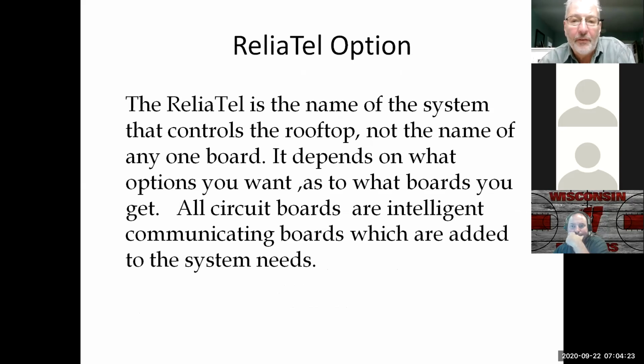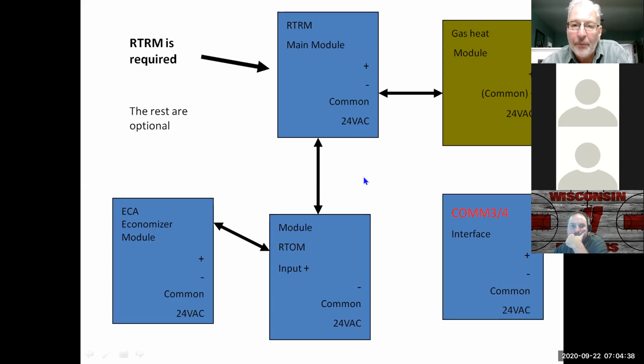All right, Reliatel is the name of the system that we're currently using on the rooftop. What it does is you can add or take out boards and configure the unit to do different things. Basically, the RTRM is your main module, and then we can add gas heat modules. We can add economizer modules. We can add input-output modules, like the RTOM, for flame or smoke detectors, freeze stats, that kind of thing. And then we can also add COM3, COM4 interfaces. We can put in LonTalk boards, BACnet boards. The nice thing with the system is the RTRM is the main control, and you can add or remove these boards, and the board will reconfigure itself to recognize the different inputs and outputs on the system.